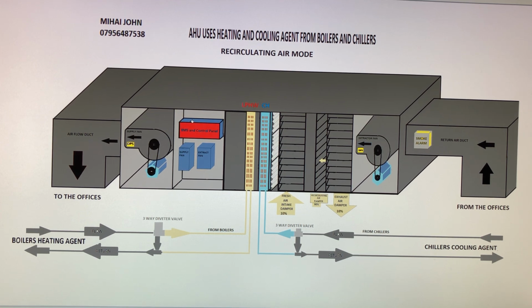When the BMS wakes up, the first thing to do is check the dampers. Now, considering the smoke alarm is okay, we don't have any alarms. So the first thing you will do, you will check the dampers. You will send the signal, and the dampers will open and close from 0 to 100% and come back to their initial position. Why would the damper do this? The damper has a motor, and the motor of the damper has some auxiliary switches.